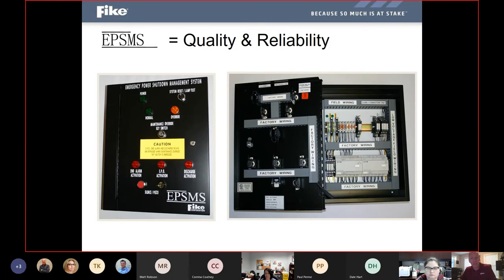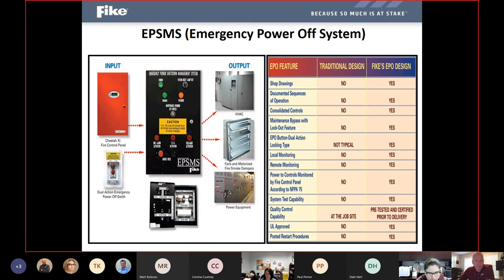So what we do is we engineer the emergency power off system so that everything is very labeled, wired, disableable to bypass for maintenance, and supervised. And with all of that documentation and schematics provided, there should be no guesswork as to what's inputting into the system, whether it's a fire panel or an EPO switch somewhere on the wall.